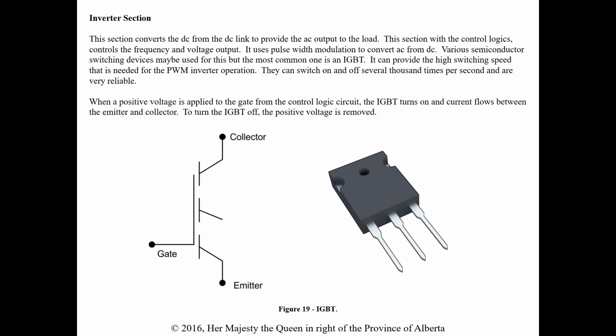The inverter section, again, converts the DC. Now we're going to get the AC output from the inverter, just like again in a UPS. This section with control logic controls the frequency and the voltage output. It uses pulse width modulation to convert AC from the DC. Various semiconductor switching devices may be used, but the most common is an IGBT. It can provide the high switching speed that is needed for pulse width modulation inverter operation. They can switch on and off several thousand times per second and are very reliable.